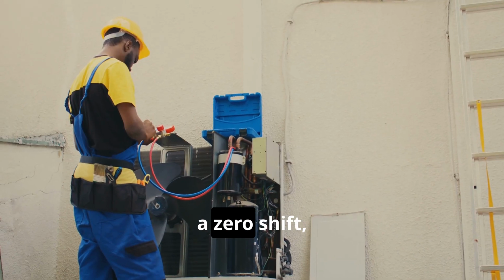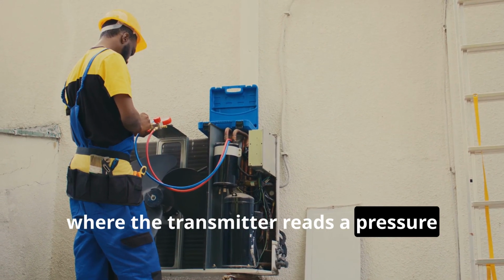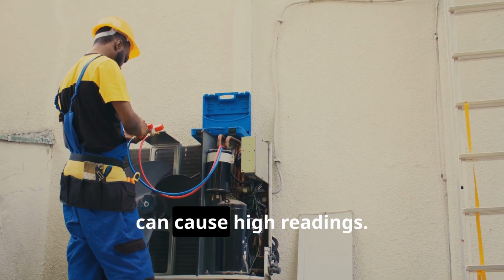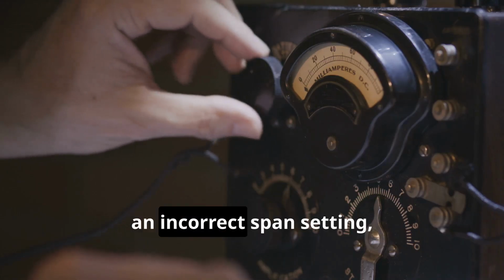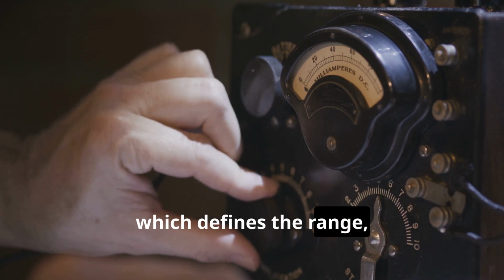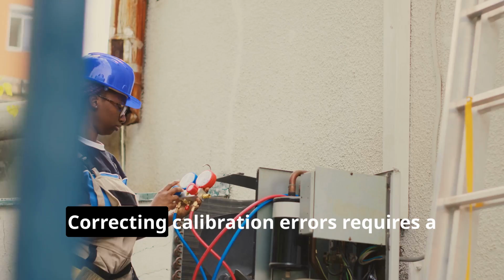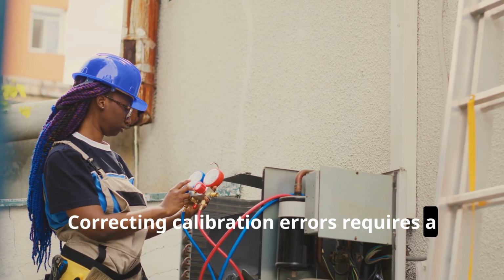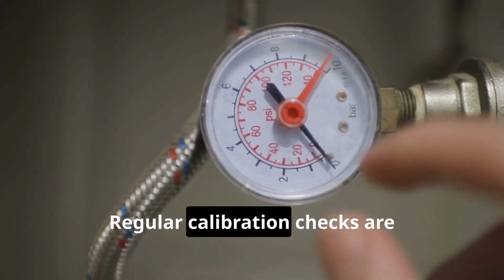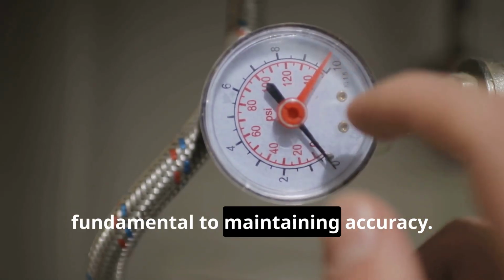For instance, a zero shift, where the transmitter reads a pressure even with no flow, can cause high readings. Similarly, an incorrect span setting, which defines the range, can also lead to errors. Correcting calibration errors requires a methodical approach. Regular calibration checks are fundamental to maintaining accuracy.